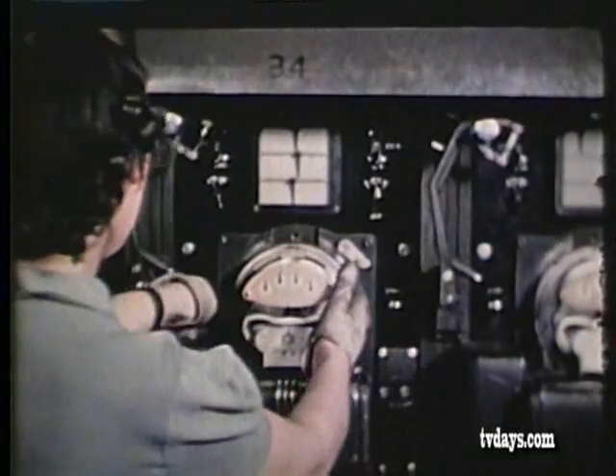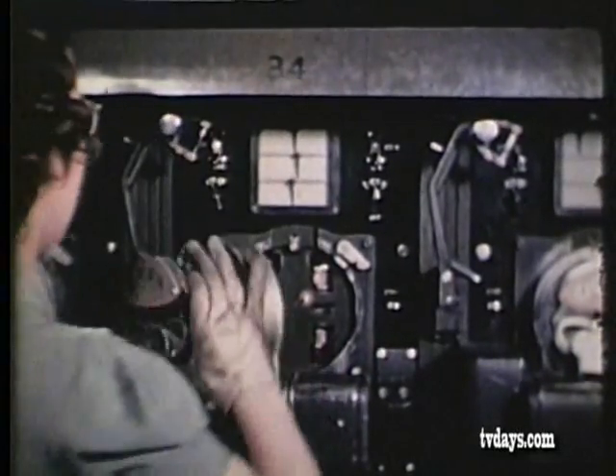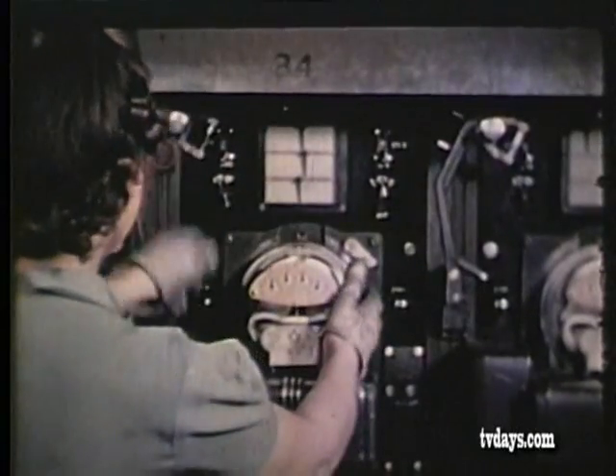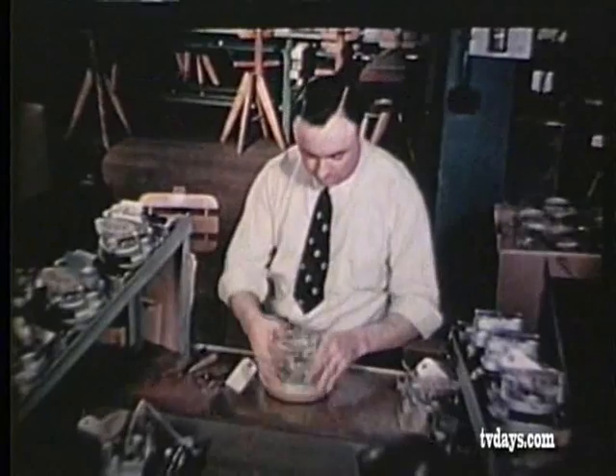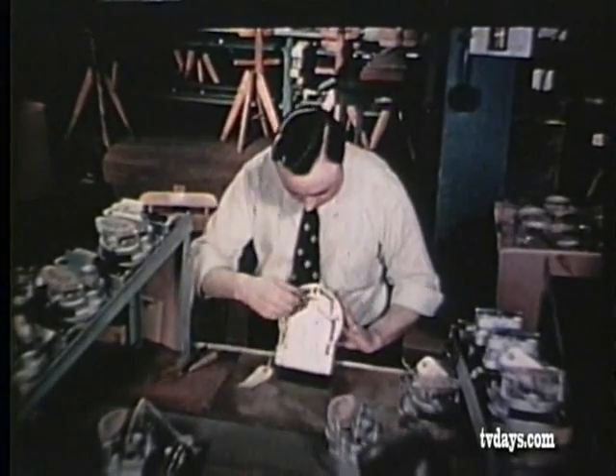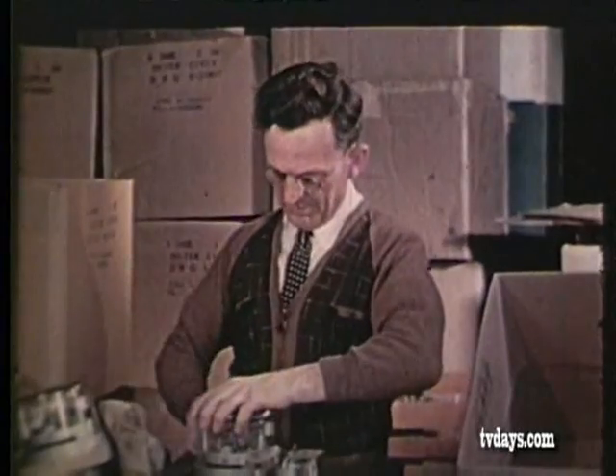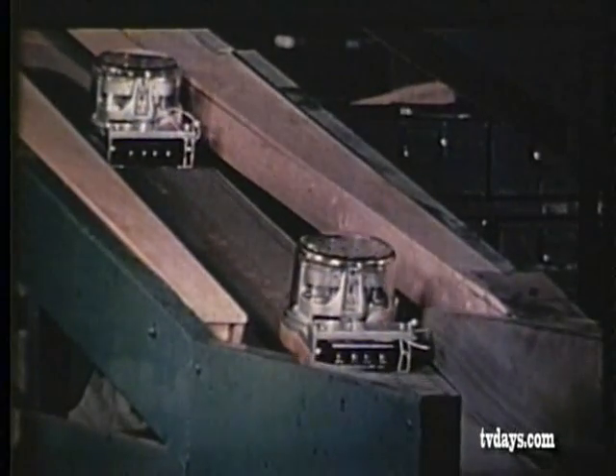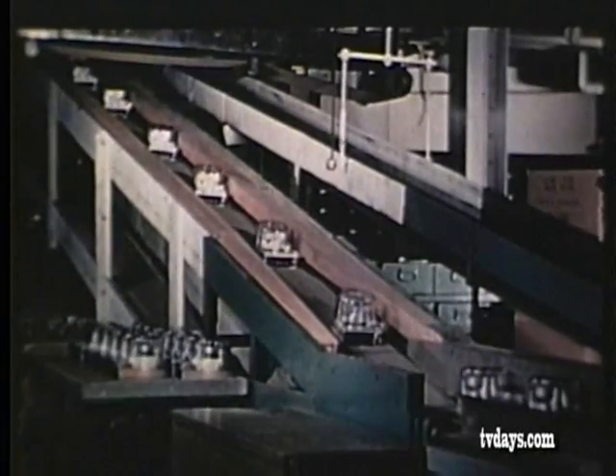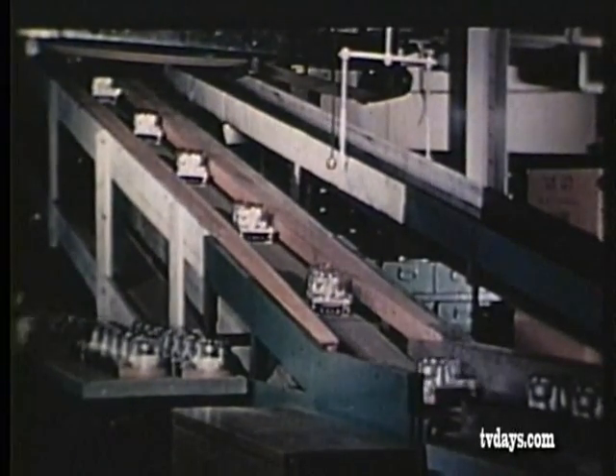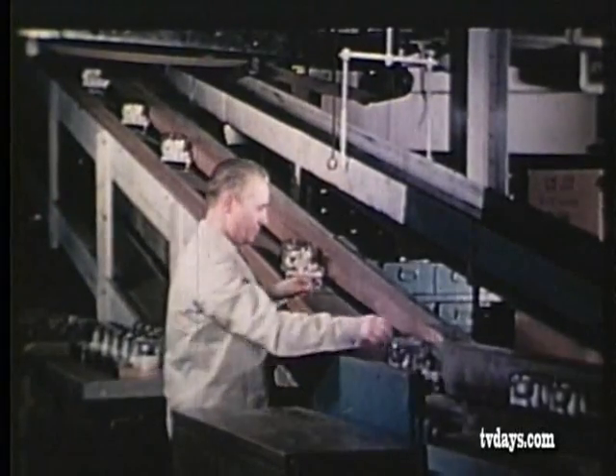Here, directly before us, the meter is mounted and carefully checked by a special photoelectric testing equipment through the use of a triple rotating standard for accurate performance under light load, full load, and lag load. The colored scales give the limits to which the operator works. The last visual inspection is made by an experienced operator. The cover is put on and the meter is ready for use. This is the wide limit watt-hour meter of today, starting its quarter-mile conveyor ride to the shipping room and the customer. And the toughest customer to please is our own engineering laboratory.